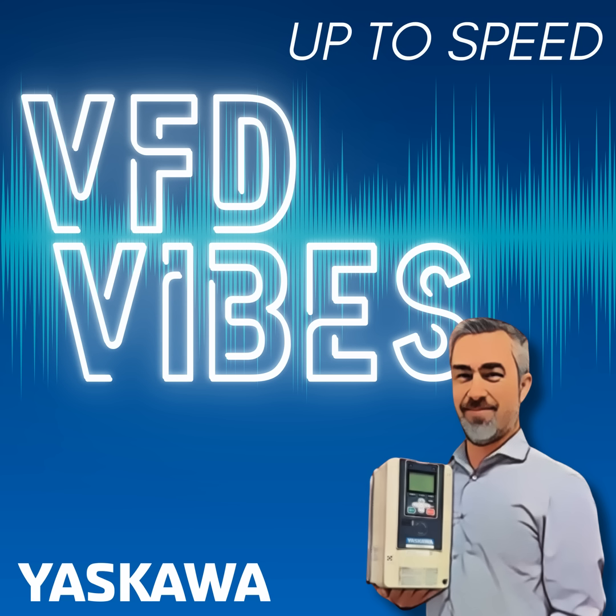My first question for you, what is available fault current, and why is it important in the context of drive installations? That's a good question, Greg. Well, available fault current is the maximum current that will flow at a specific location on a circuit under short circuit conditions. For example, when a branch circuit feeds an electrical panel or device, the amount of short circuit current available to that panel or device is what's referred to as available fault current. It's important because panels and devices are required to safely withstand the amount of fault current available at that location.